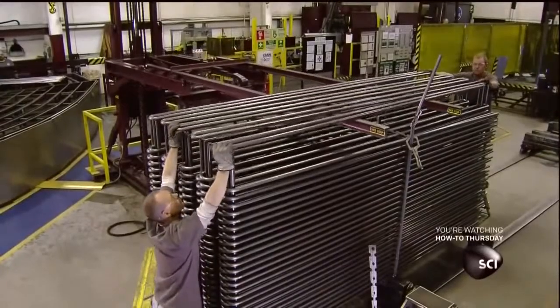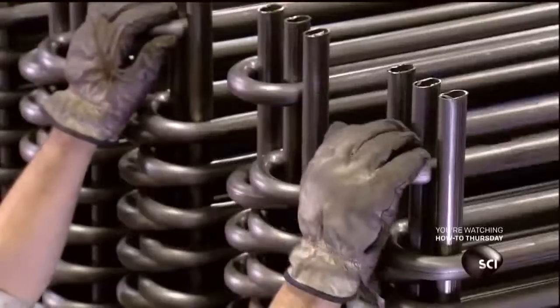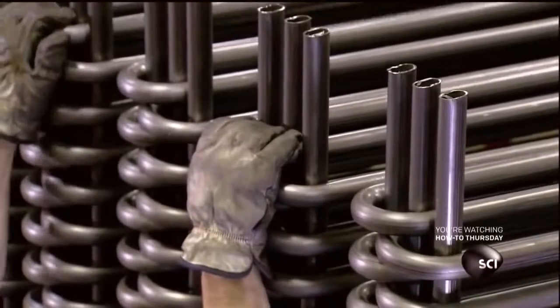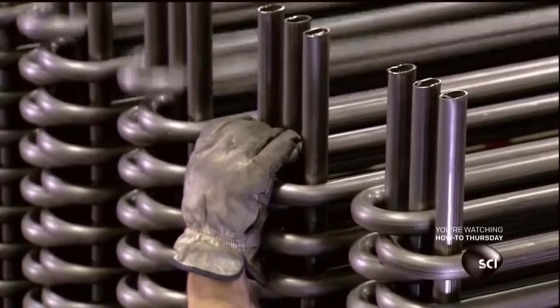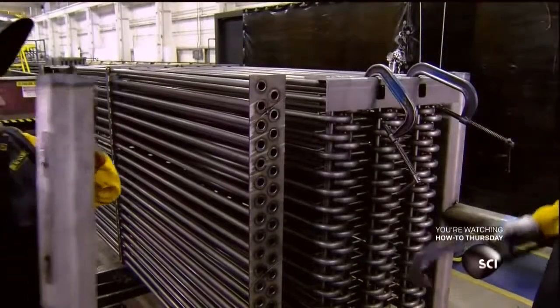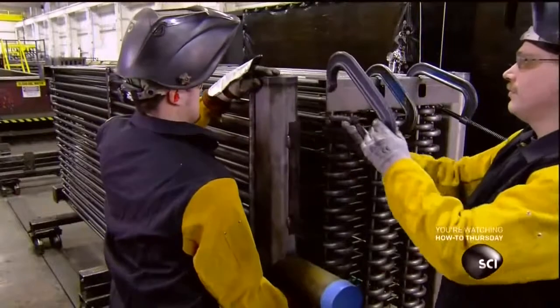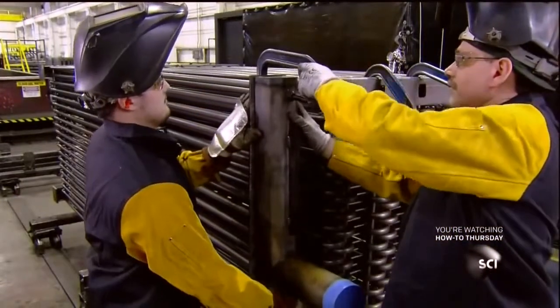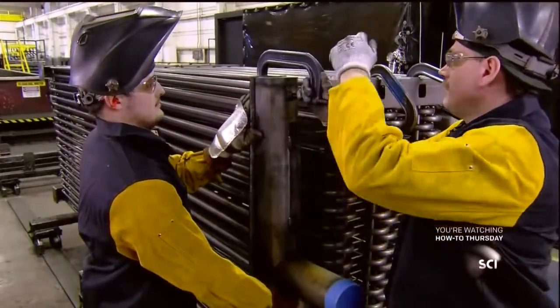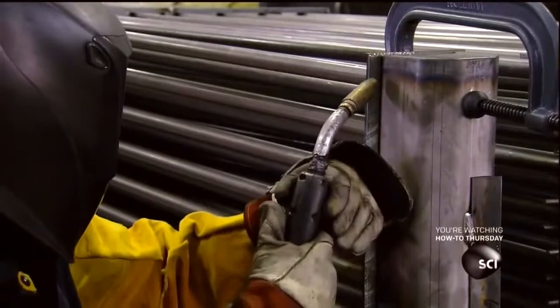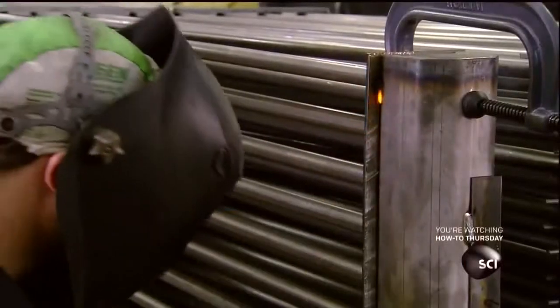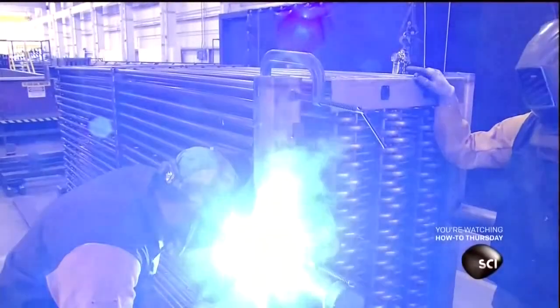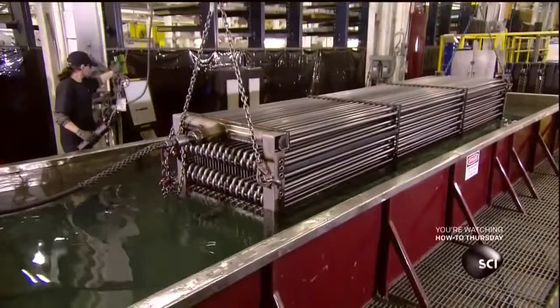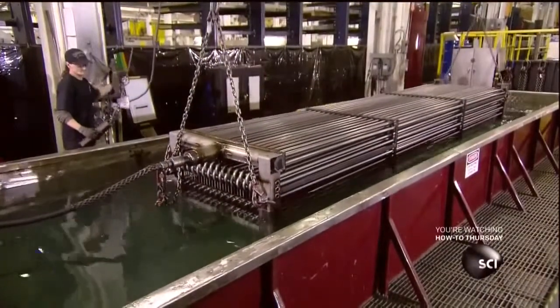Once all the circuits are ready, workers stack them on a frame. Then they weld the tube ends to the corresponding holes of a steel plate. They close up the plate with a cover called a header. After clamping the header in position, they weld it in place, forming a pressure-tight seal. The coil is now fully constructed and ready for testing.